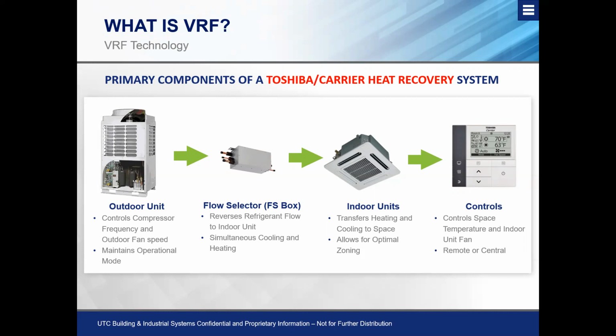So one of the biggest advantages of using a single port box is that we provide power and communication from the indoor unit, which means we don't have to run a separate power source or communication wire, because those bundles come with that flow selector box to automatically hook up to that indoor unit to power it, and also to be able to communicate with the indoor unit, so a heating or cooling call to a solenoid can open as needed.